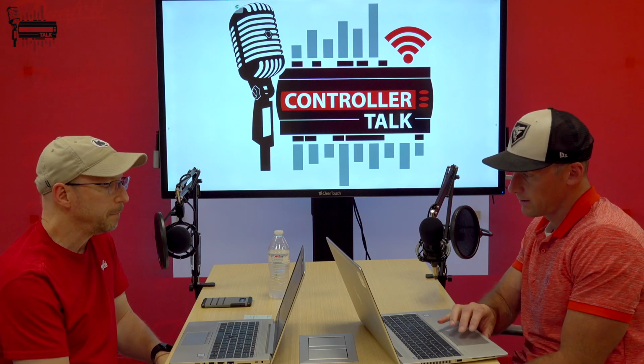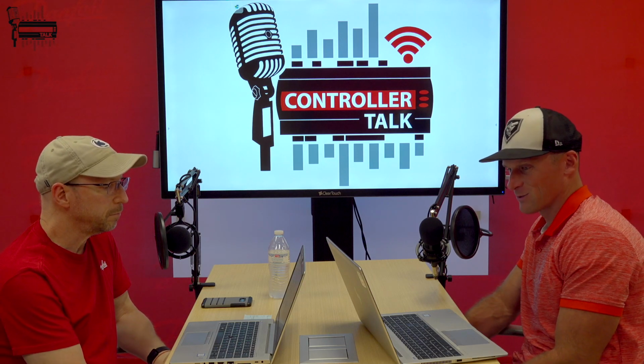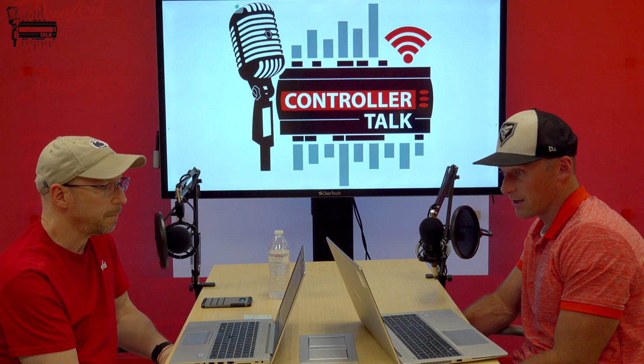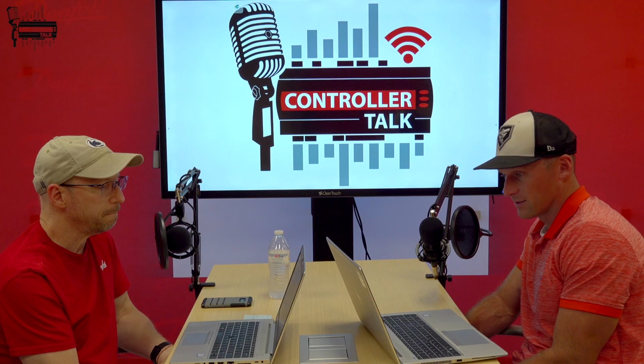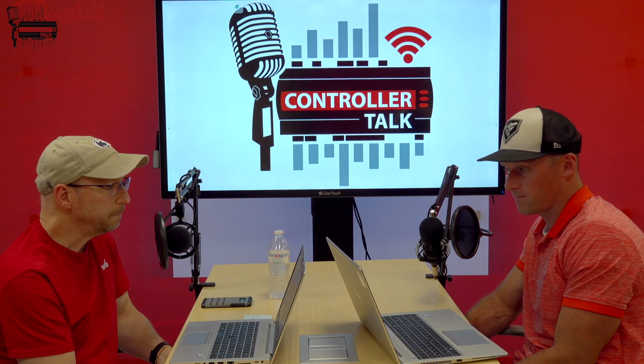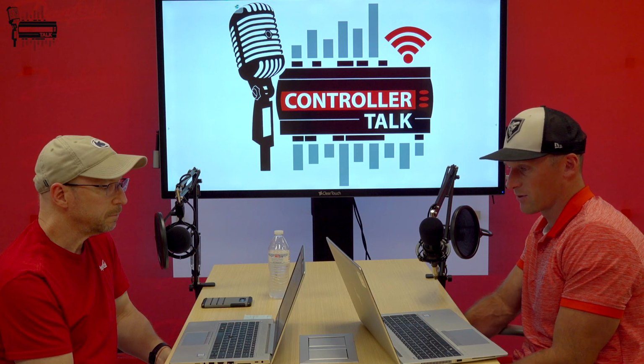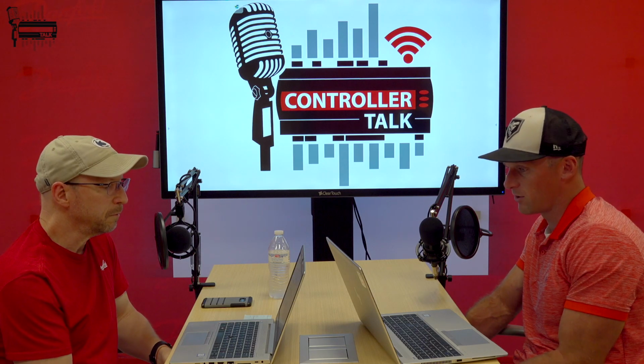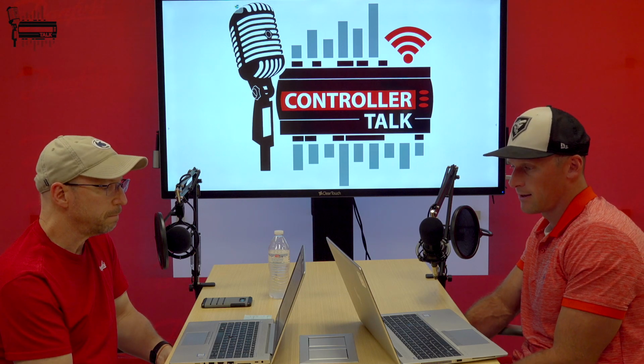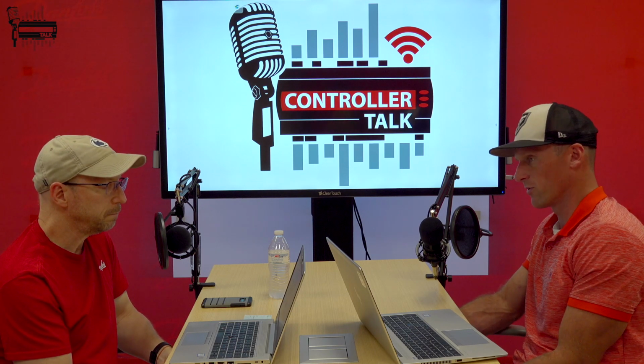Yeah. And then we'll get into the one on the other end of the spectrum that we see very little of, but it is there. It's the 783A. So this is our Cascade pack controller. This one's pretty flexible from the refrigerant side, where it could be HFC, CO2, ammonia. It could be a lot of different combinations there. But this one's assuming that it's taking control of the compressors on both sides of the Cascade heat exchanger, the low temp and the high side. That can be up to 8 compressors on either of those two sides. And then the pack controller also assumes it's taking control of the electronic expansion valve that's feeding the Cascade heat exchanger between the two refrigerants.